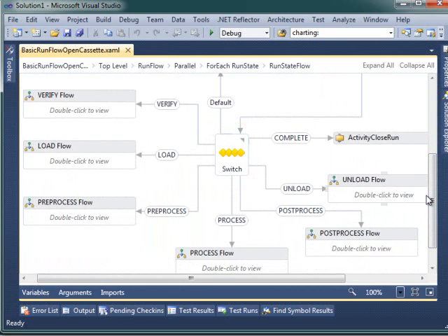The logic for a state is contained within its own flowchart construct, which may be empty if no custom logic is required. If there is no branch for a required state, the state is just logged and the loop moves on to the next state. Since the required states for a run are configured on the Equipment Manager component, the mechanism allows a superset of predefined states to be handled by the workflow, but only specific ones enabled in the Equipment Manager configuration, as required.